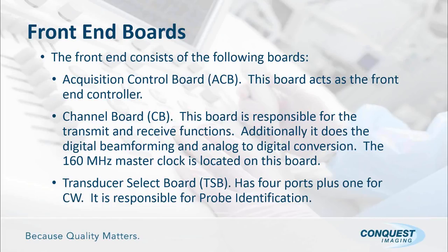The second possibility is, let's say you've taken that probe and put it in a separate port and it still doesn't ID. You've tried another probe. You can start seeing how we can troubleshoot. Is it the probe or is it the transducer select board?